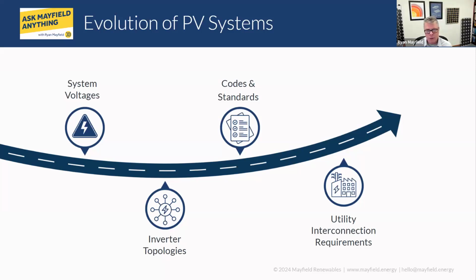I see somebody asking about restringing of arrays. The system voltage is important, but a very large part of this focuses on, say you're replacing an inverter and keeping the PV modules - what is the voltage of those modules? If you get into some early 2000s era modules, they're likely only 600-volt modules, so you can't restring them even if you bring in a new 1,000-volt or 1,500-volt inverter. The module listing is an important part of it.